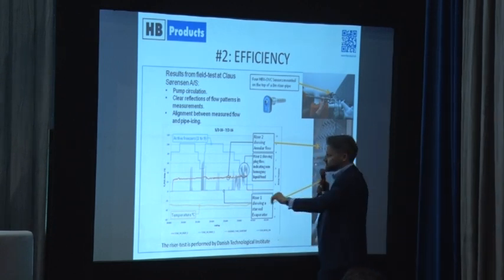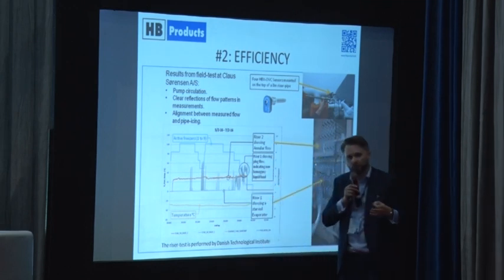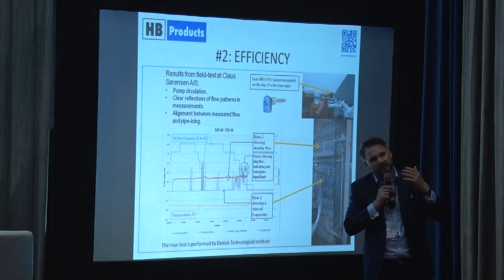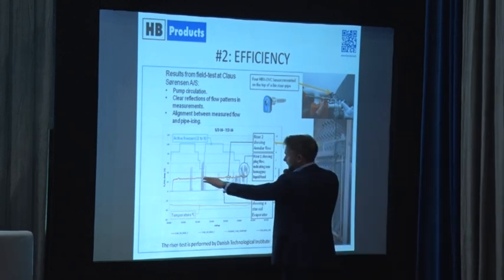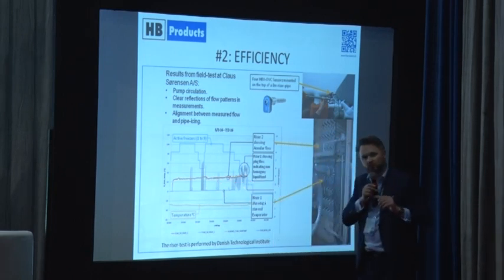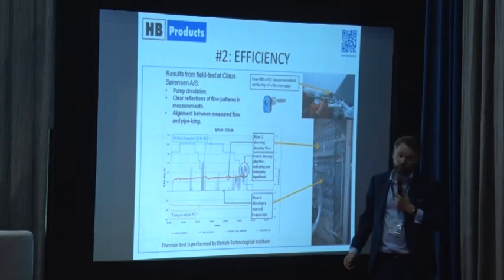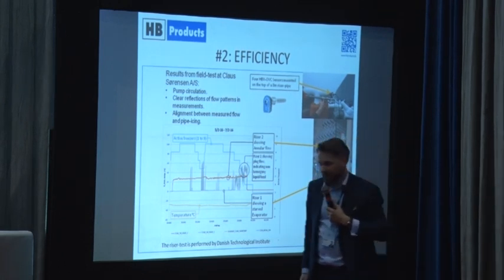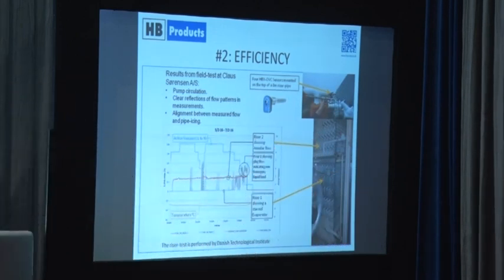On evaporator number two — the orange line — luckily we had a much more stable and very fine pattern as we wanted. There are no liquid slugs, no drying out, no pressure drops. This is the picture we want to see. Unfortunately, one evaporator was working well and one was non-working in this freezing tunnel operating at minus 35°C.